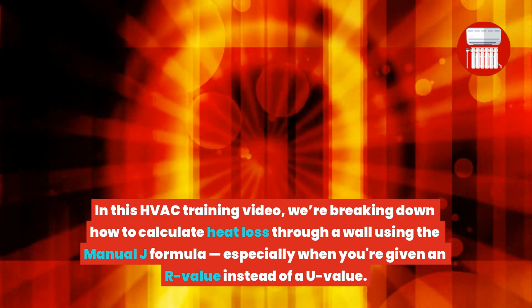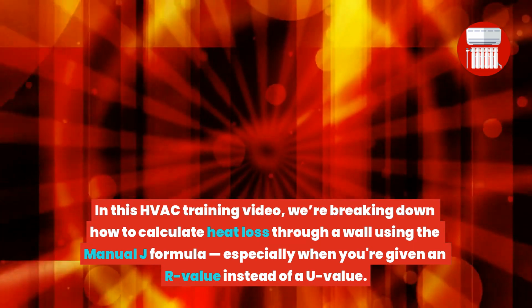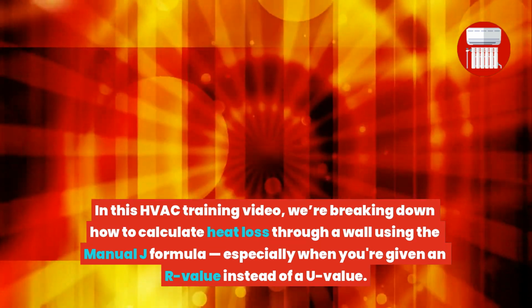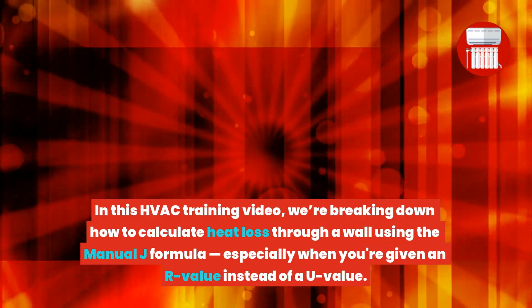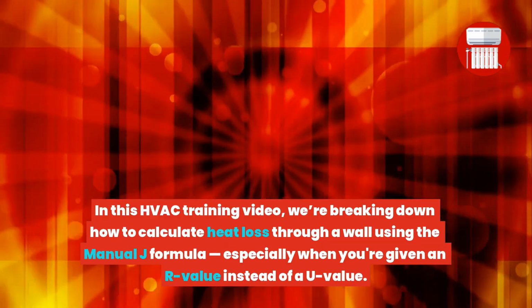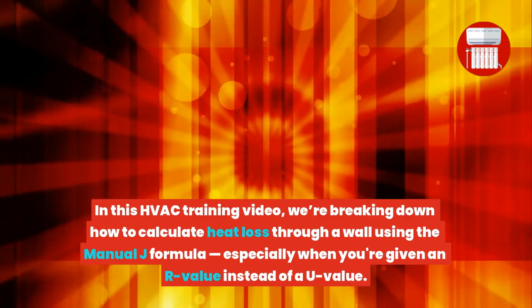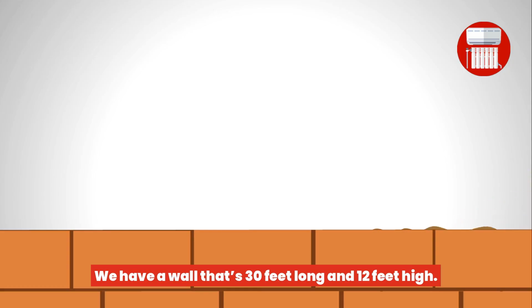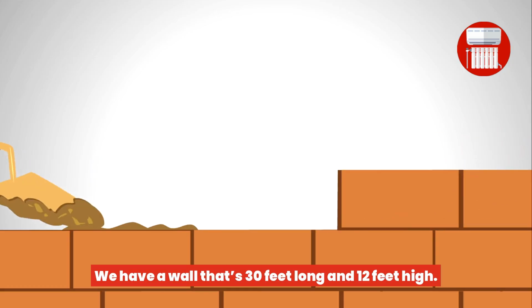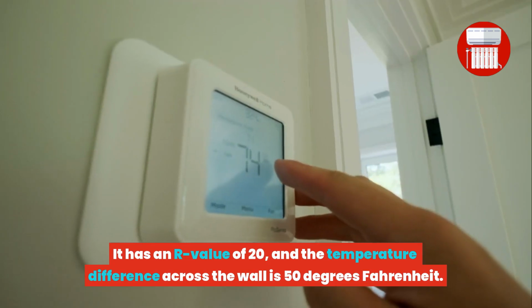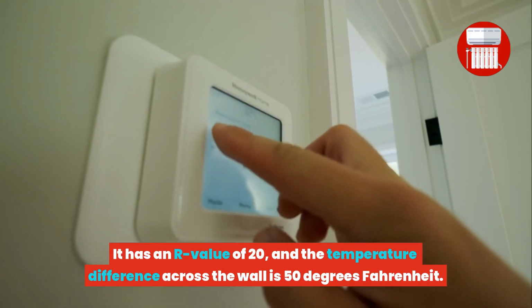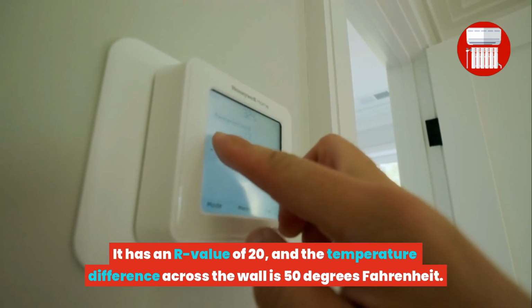In this HVAC training video, we're breaking down how to calculate heat loss through a wall using the Manual J formula, especially when you're given an R value instead of a U value. Let's walk through a real example. We have a wall that's 30 feet long and 12 feet high. It has an R value of 20, and the temperature difference across the wall is 50 degrees Fahrenheit.